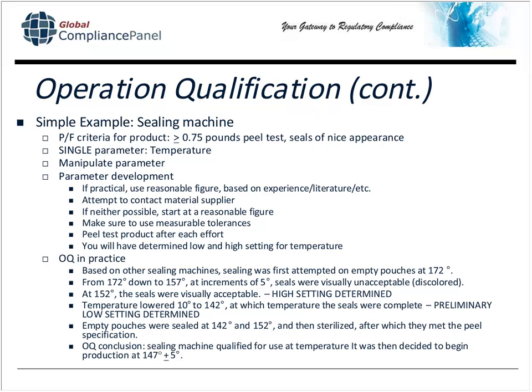And what we're going to have is product that is not strong enough at the low end, and product that is burnt, where the temperature is so high that it burns the pouch. It looks almost blackened. So in practice, hypothetically, we have other sealing machines at this company, and so we know that we're going to seal empty pouches at 172 degrees. Just because I have something in my pouch doesn't mean the seal appearance or seal strength will look different. It's a little bit naive to think that because I have my plastic accessory or 12-inch long tube set in this pouch, it's going to provide such a force that I'm not going to get accurate empty pouch sealings.